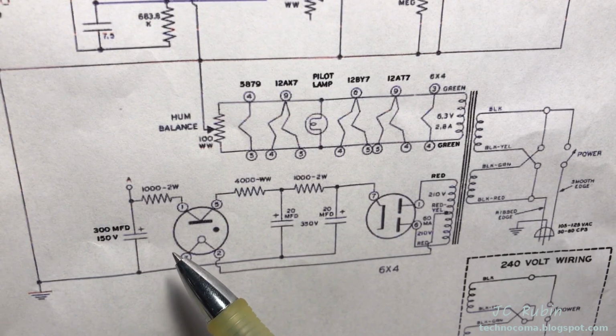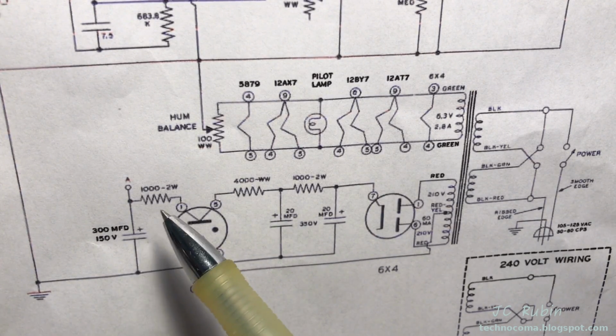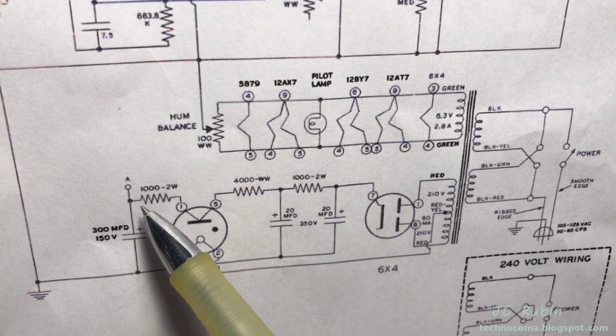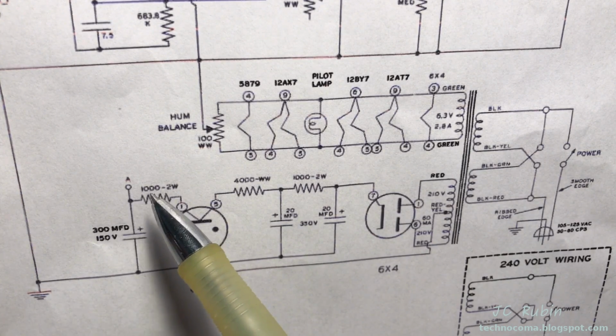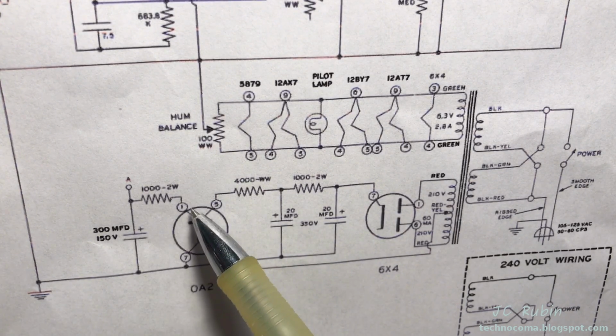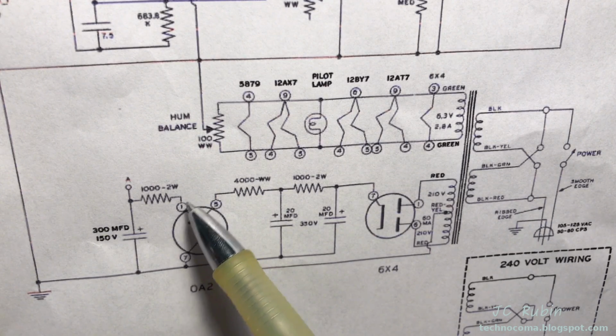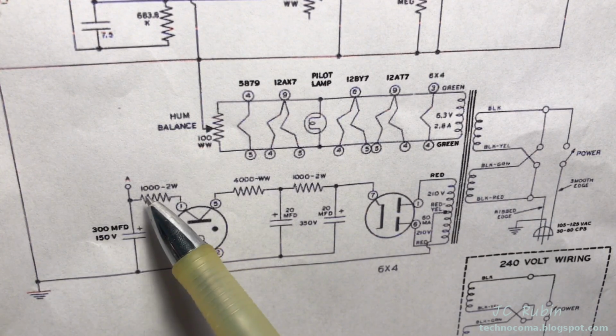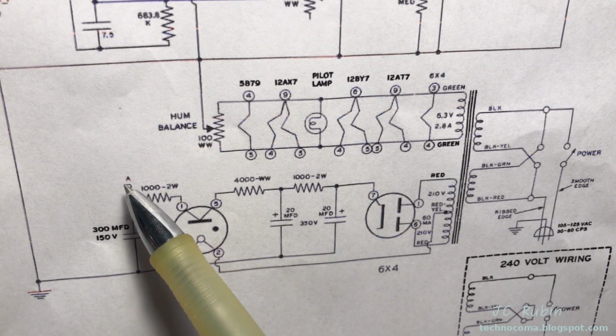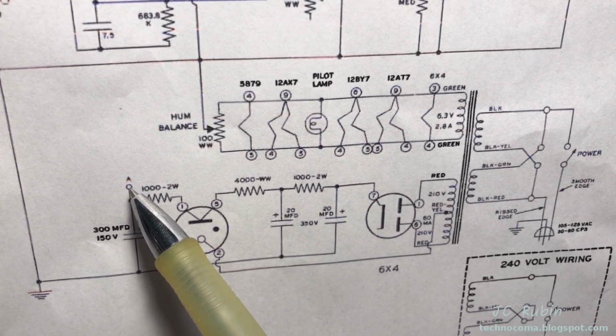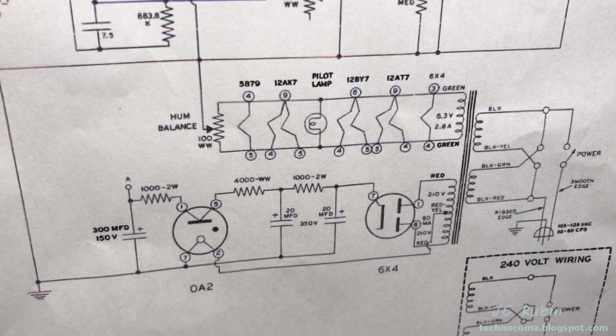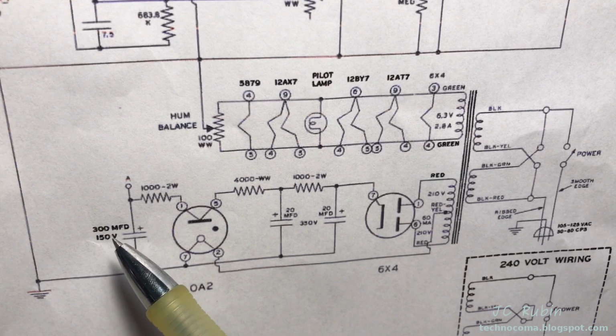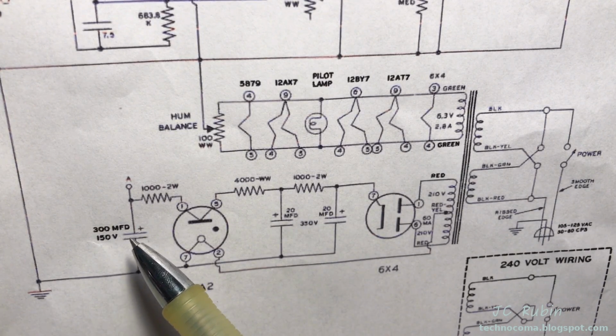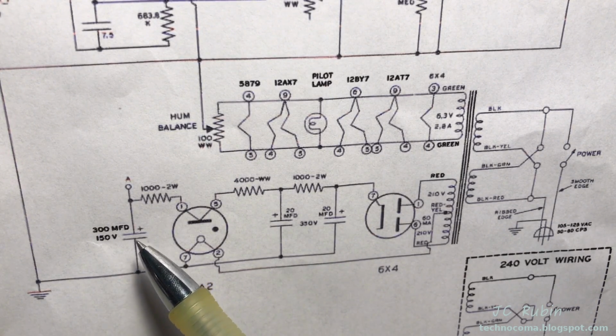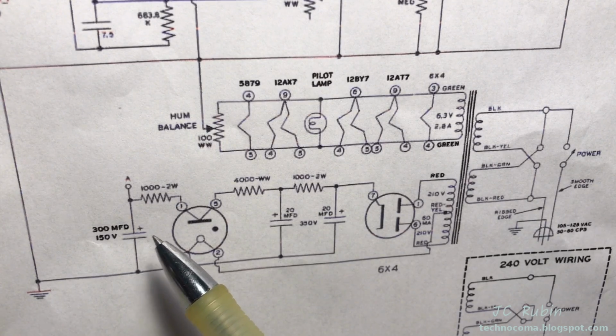It is an extremely filtered, extremely stable, 150, not 150 volts, but whatever the pin 1 is minus this voltage drop here. I got a listing somewhere. But whatever it is, it's an extremely stable, extremely clean DC voltage. Right, and I got this 300 microfarad capacitor that's sitting in there, and I don't have a 300 laying around to replace it.